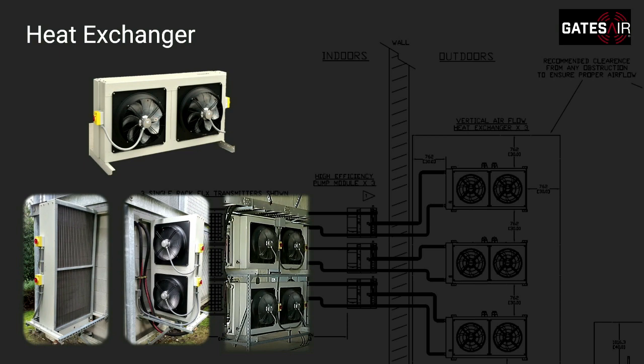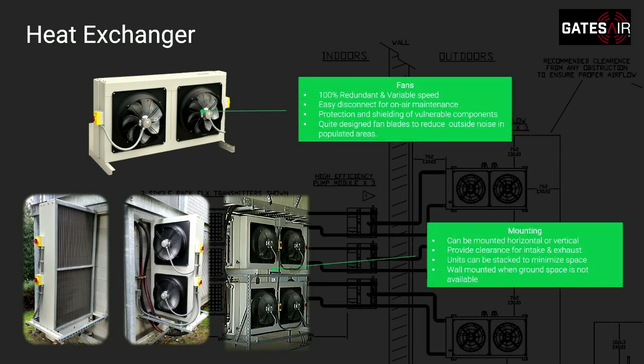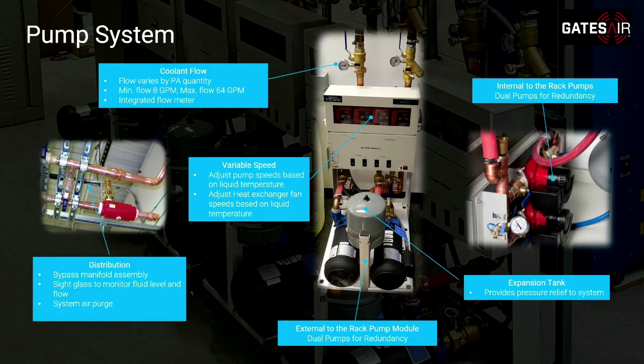Heat exchangers. We can put these in many different locations. We can do a lot with them. As far as mounting is concerned, in other words, we can mount them right to the side of a building. We've mounted them on top of the building. We've actually stacked multiples, typically up to 3 high is what I could do. I don't like doing 3, I like doing 2 because it's a little hard to get to the top one. But the point is we've got multiple options for that. Now, what is the downfall of a heat exchanger? I still have to protect that heat exchanger from tower icing and all that, unless you live in a place that doesn't have icing. But I've seen ice in Texas, so it happens. That goes back to the pump systems again, internal, external, okay, all of that's available.